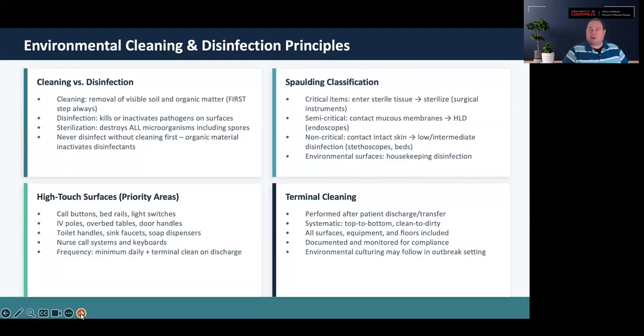And we have to make sure that we follow the contact time, right? So contact time is the total amount of time that's necessary to kill all the organisms that we're targeting. So let's say that there are 60 organisms on the product's label, and the longest contact time is 3 minutes, right? There may be other product claims on there that say 30 seconds or 2 minutes, but if the longest contact time is 3 minutes, then that's the contact time that we're going to follow, right? Because we want to make sure that we get total microbial kill for the organisms that we're targeting. So again, cleaning is removal of bioburden or soil, disinfection is going to inactivate or kill the pathogens.